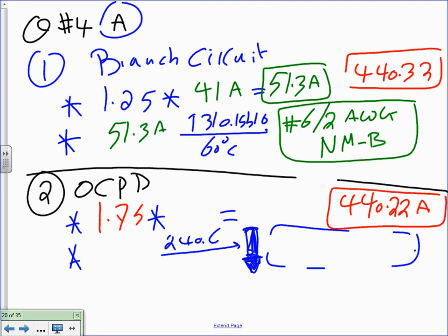Okay, the same thing, overcurrent device. Overcurrent device, Brian, my friend, 1.75. This is not from my basement. This is directly from 440.22(A). It tells you to multiply for the overcurrent device because of the inrush and because of the special characteristics and operation mechanism of the HVAC equipment, the heating and cooling. Multiply by 1.75 to account for the inrush and so forth. So that will give me 41 times... Who's my favorite gentleman who's going to give me the answer? 1.75, 71.8. Second? 71.8. Did they hear a second?